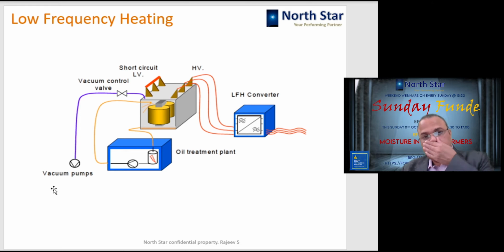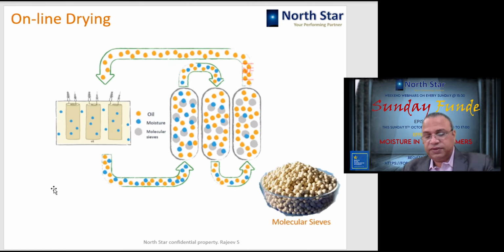It is very effective as far as drying is concerned. One big drawback of the older technique is that you end up absorbing the gases we use in the dissolved gas analysis, so those gases also get removed. In this system, that does not happen, because the dissolved gases in the oil remain, as we are not filtering the oil through vacuum. So those gases will remain as they are, and when you do the DGA, you will get a true picture. So this is low frequency heating.